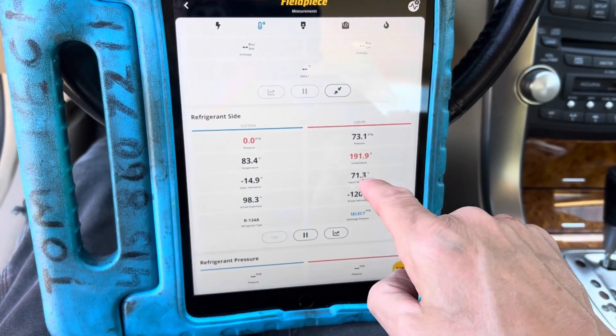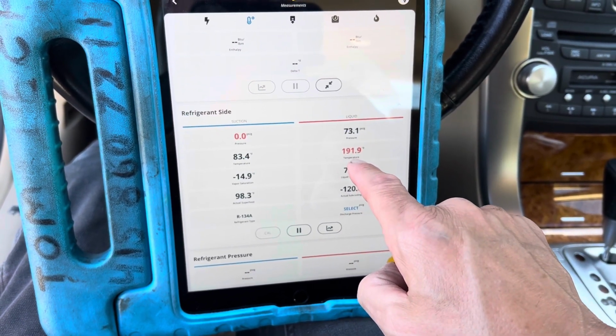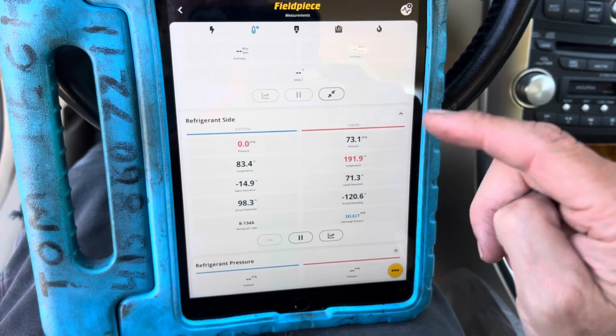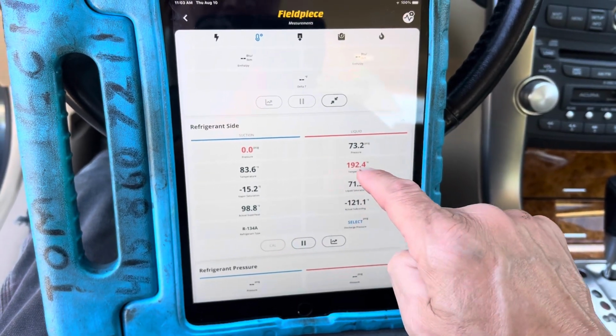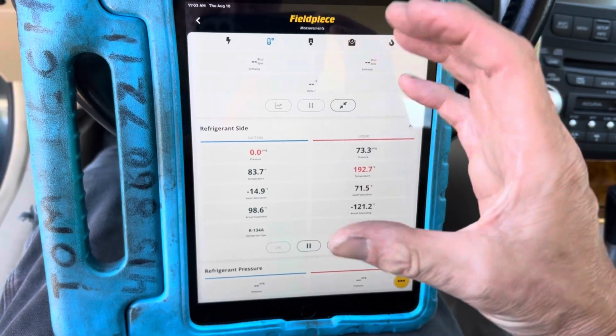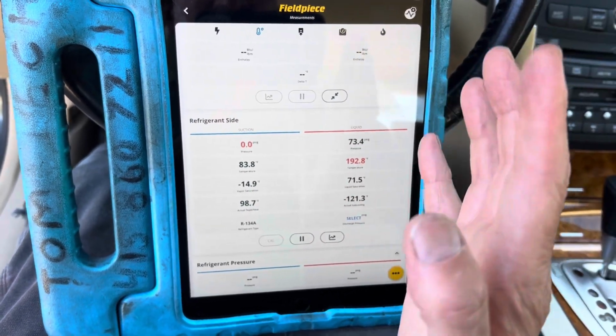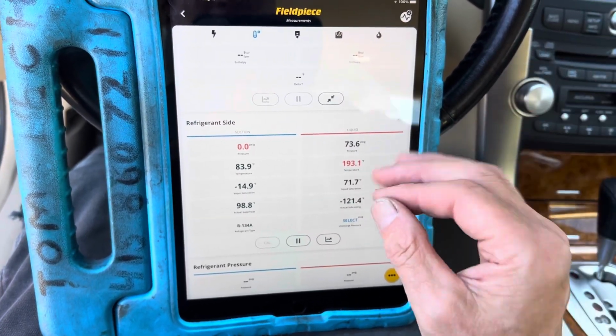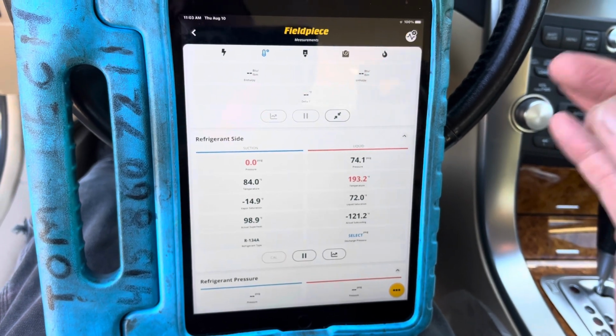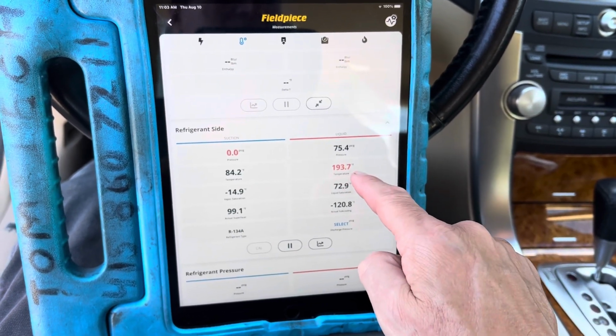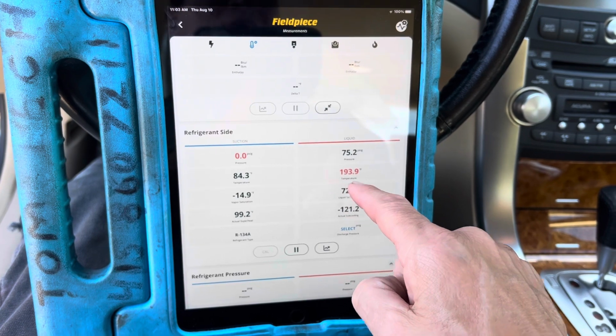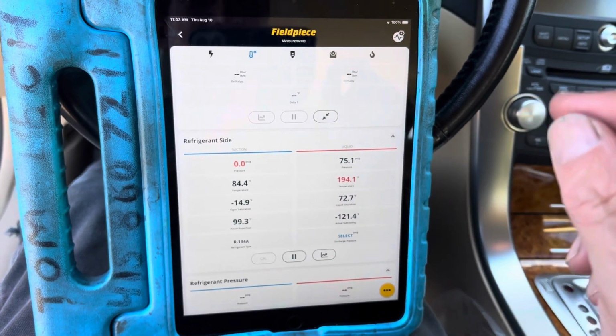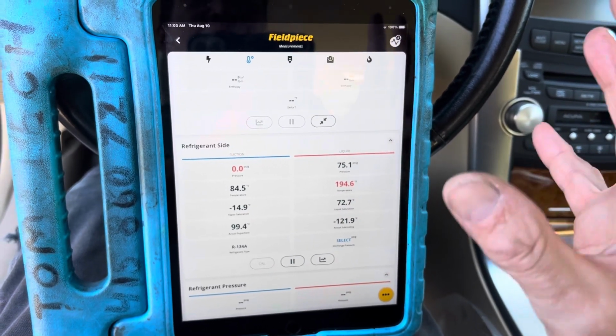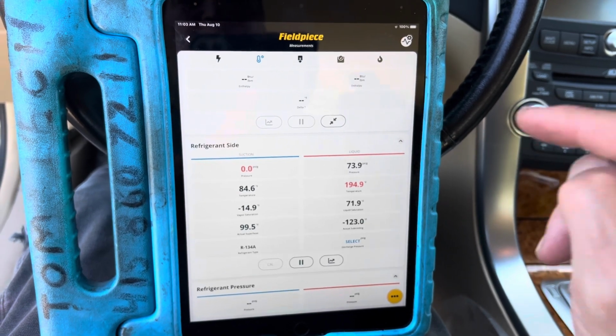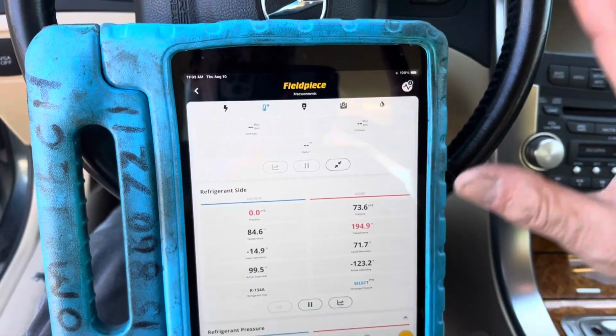Oh, look, we're up to 191 degrees. So I'm several inches away from the compressor right now. Whatever this temperature is, the inner core at the compressor and at the cylinder walls and everything on the oil film is roughly 50 to 75 degrees hotter than what shows here. So we're approaching 260 degrees or so of surface temperature. This is approaching the oil breakdown and burn down point right now. And this is a cold day with no heat load.